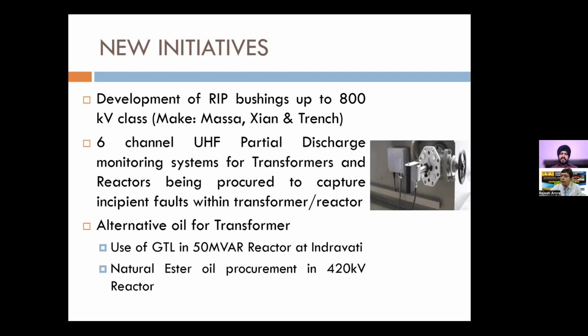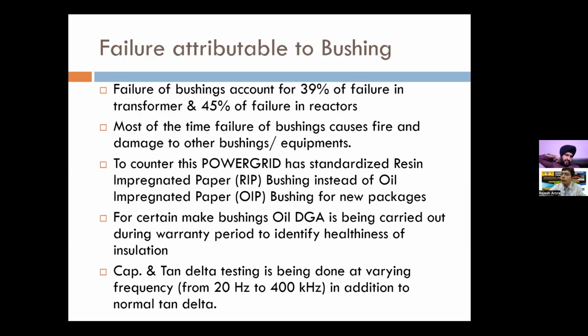And another thing is that we have also experimented with alternative transformer oil, as in natural ester oil. So world's first 420 kV natural ester based reactor was charged in India at Maithan substation of ER2. We have also used GTL oil, gas to liquid oil, for one reactor at Indravati. So all these new initiatives have helped us in bringing down our failure rate, because we have standardized the RIP bushing. So the failure due to bushing failure has been reduced.